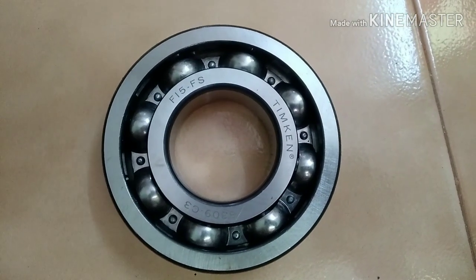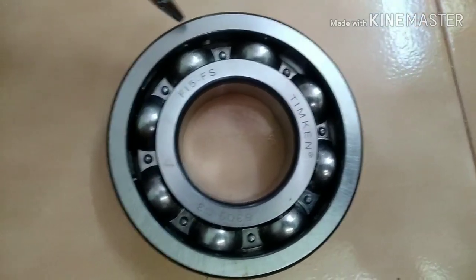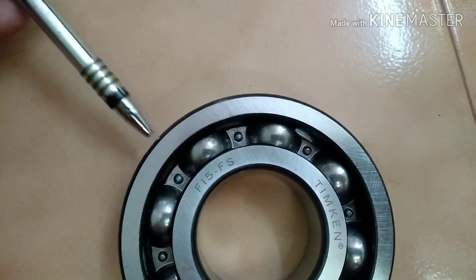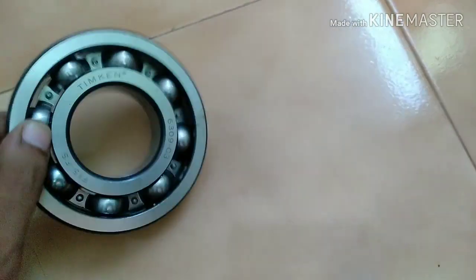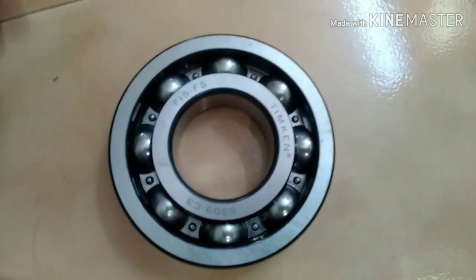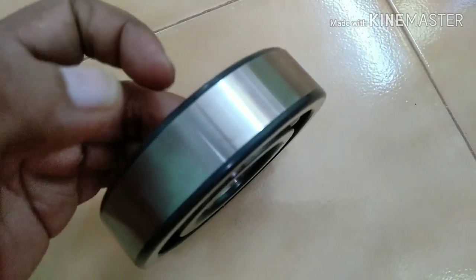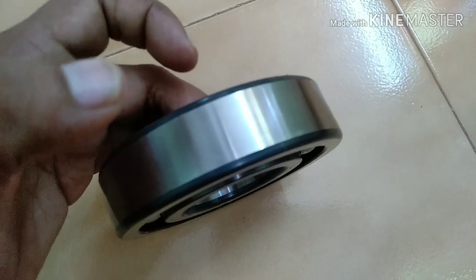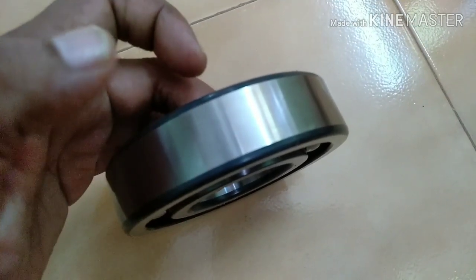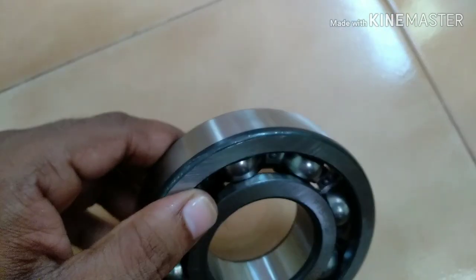We must know the temperature of the bearing. We can either put a probe on the surface of the outer race or on the surface of the inner race. The most practical and easiest method of knowing the temperature of any bearing is putting the probe above the outer race, so placing the probe of your BTD — Bearing Temperature Detector — on the outer race will let us know the bearing temperature.